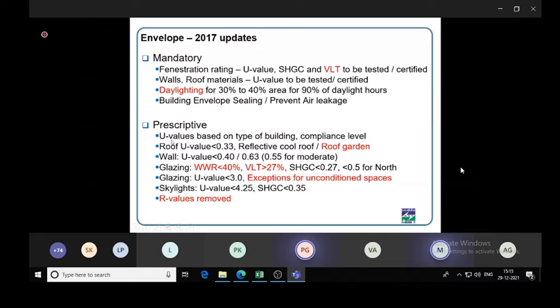In prescriptive requirements, the U values have been given. For the roof, it should be less than 0.33, and we should use a reflective cool roof or roof garden. Wall U value should be less than 0.4. Again, if it's a different climate like Bangalore, then slightly higher values are allowed. The glazing window to wall ratio should be less than 40%, VLT more than 27%, SHGC less than 0.27.